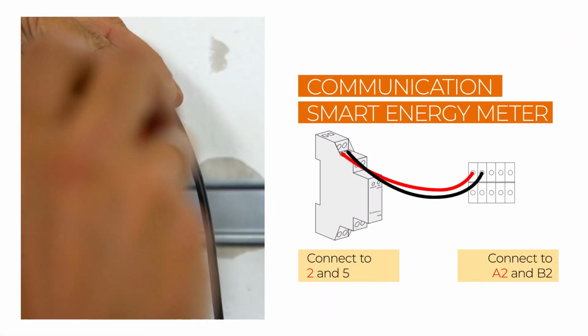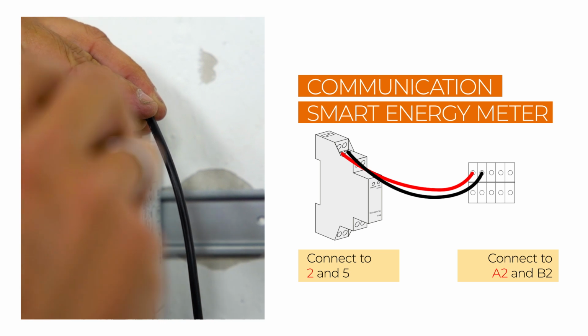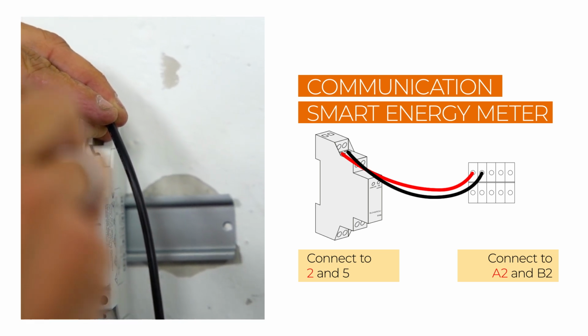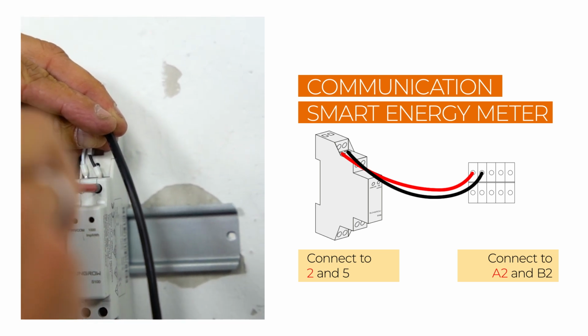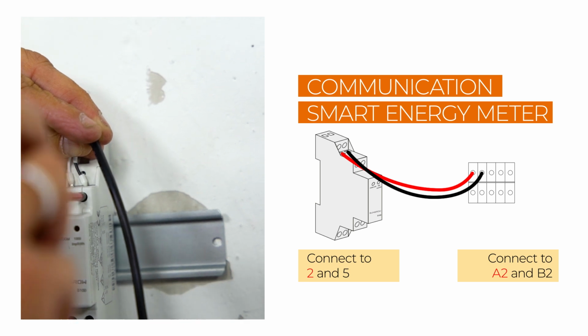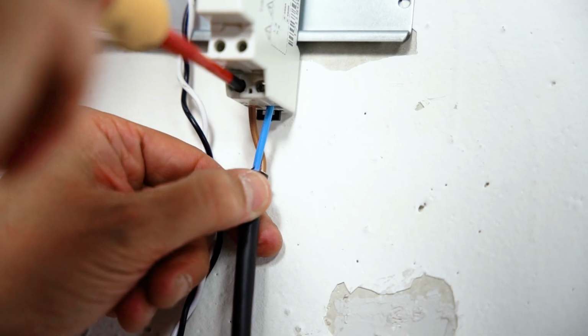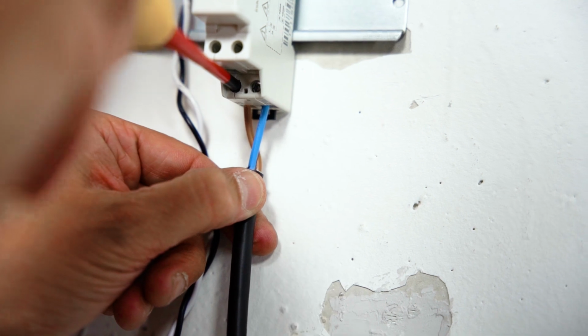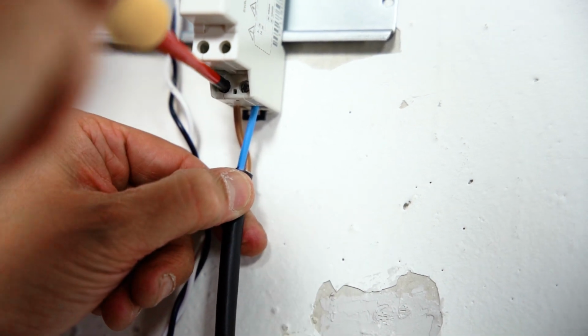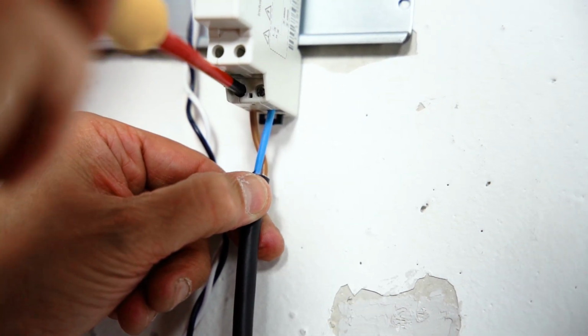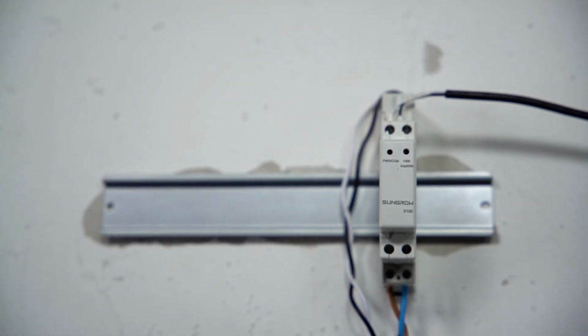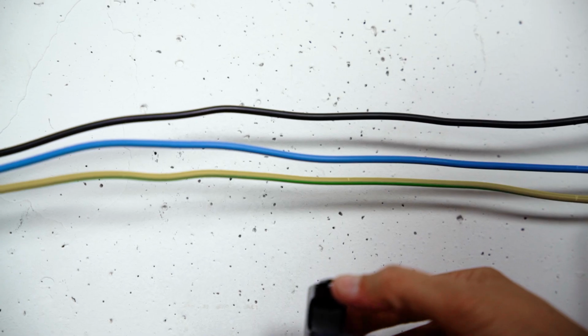Now, let's connect the smart energy meter itself. Mount the meter on a DIN rail and connect the communication cable RS485A to pin 2 and RS485B to pin 5 on the meter. The meter must be supplied with 230 volts. Connect the line cable to pin 3 and the neutral cable to pin 6. The CT of the meter must be clipped around the house line cable.